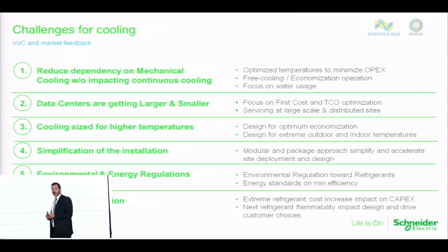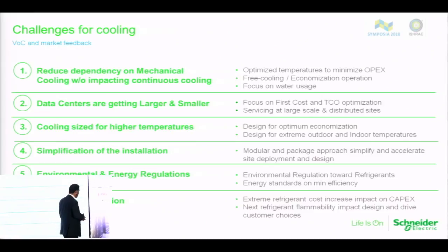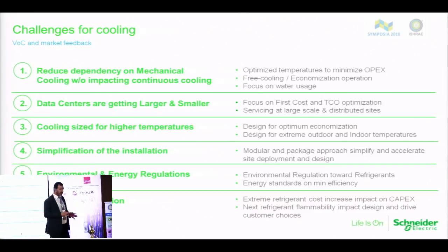Many economizer solutions are based on water. That's fine. Water is a good point to reduce, and adiabatic systems are a good strategy to reduce energy consumption, but we need to be aware that water is something important in our life. So we definitely need to reduce the mechanical cooling, but we also need to preserve water consumption, because data centers are getting larger and larger.